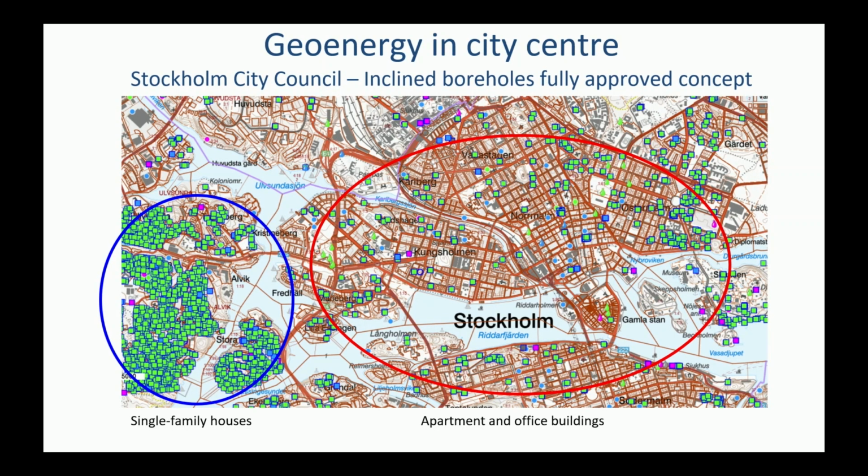I should also mention that in Stockholm, center of Stockholm, inclined boreholes are a fully approved concept. So the designs or the intended drilling is delivered to the environmental office of Stockholm City, and they will approve it. You can see here inside red, that's the center of Stockholm. There are lots of installations, and they are fairly large. It's apartments and office buildings, whereas to the left you can see some of the suburbs of Stockholm where you have single family houses, and in that area almost all houses have a ground source heat pump.